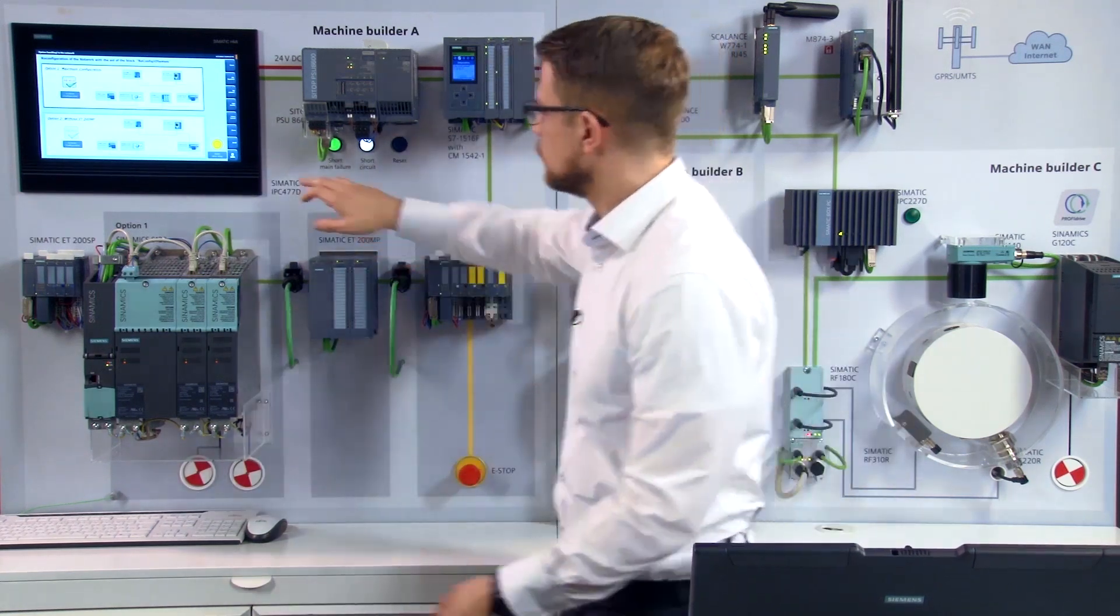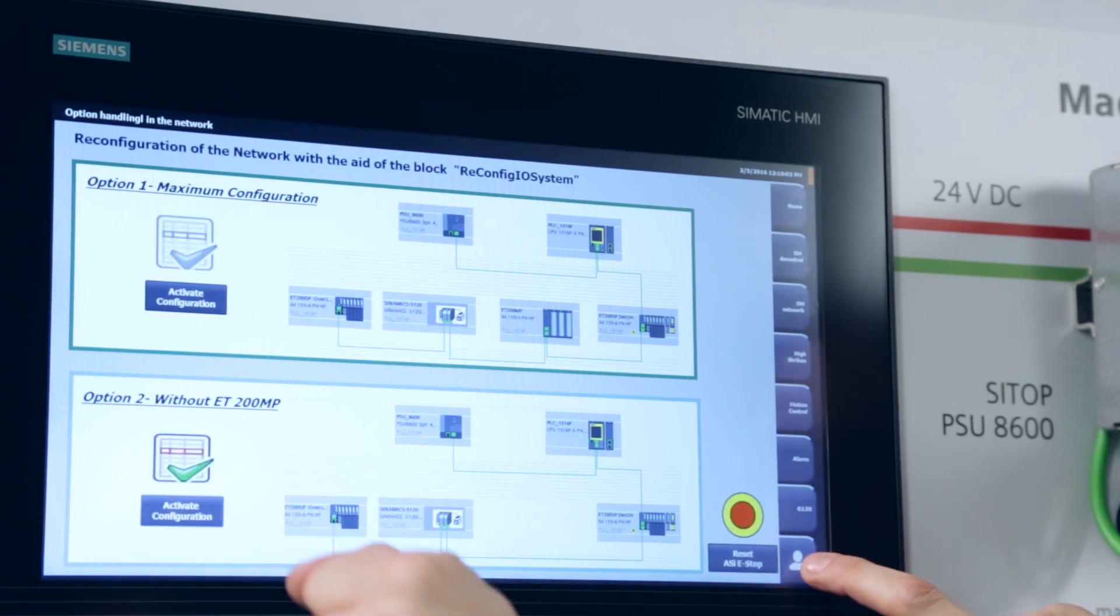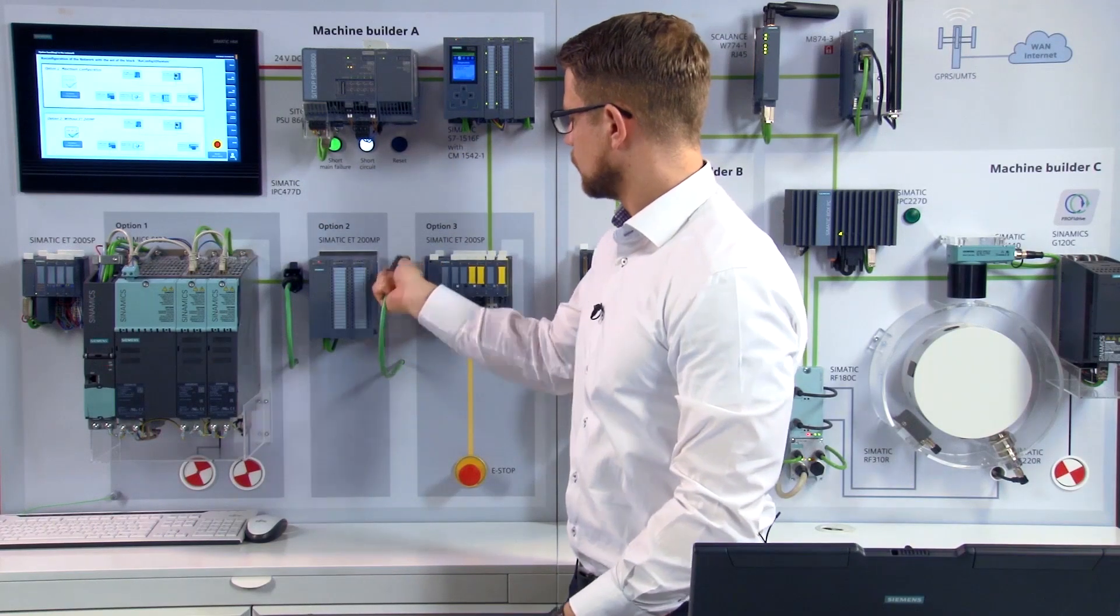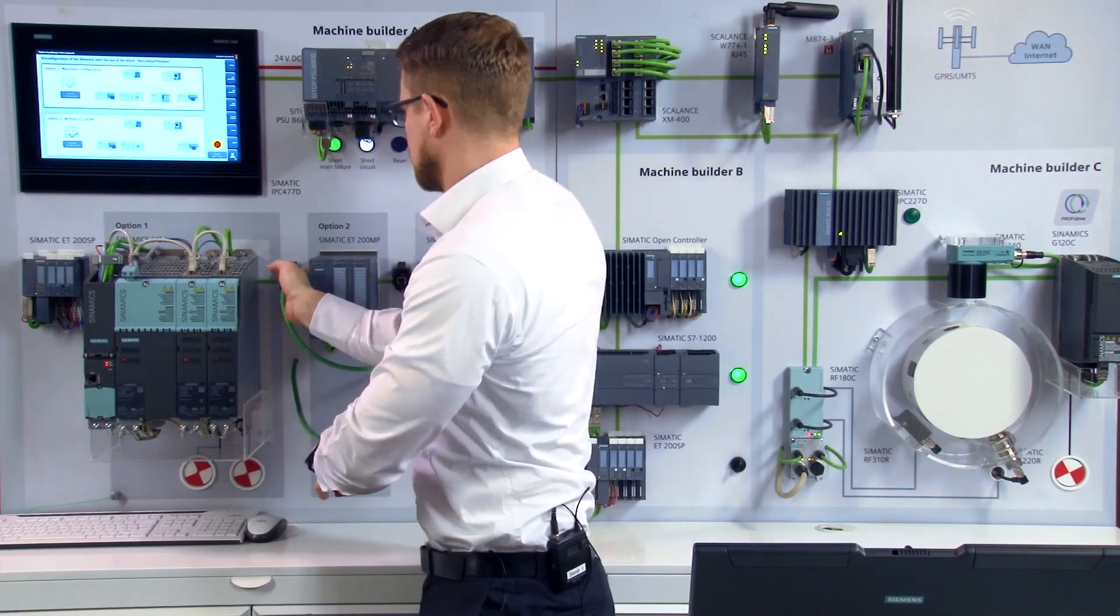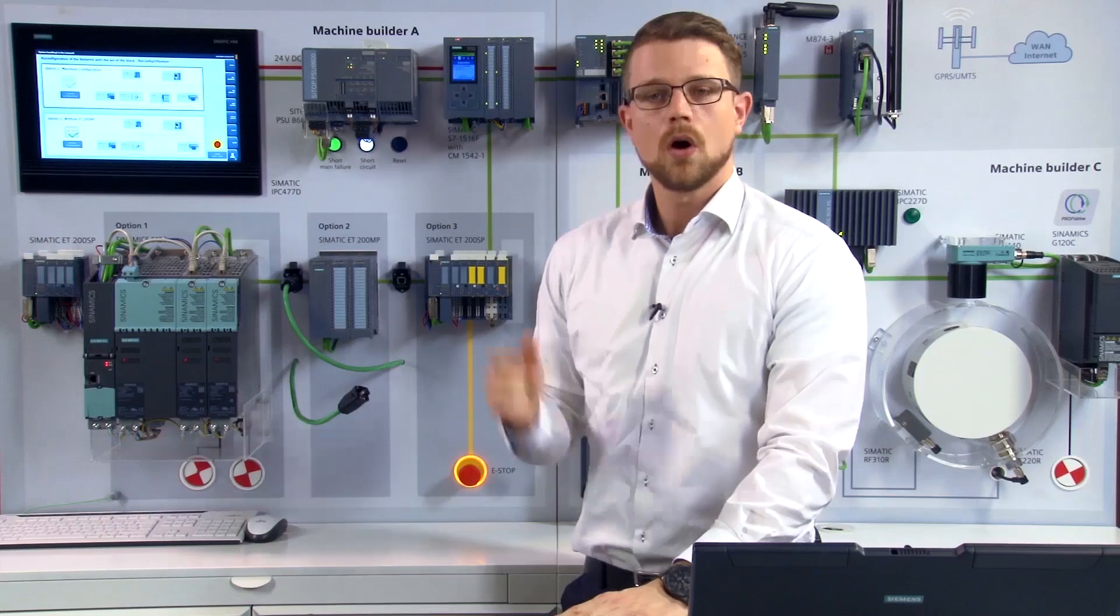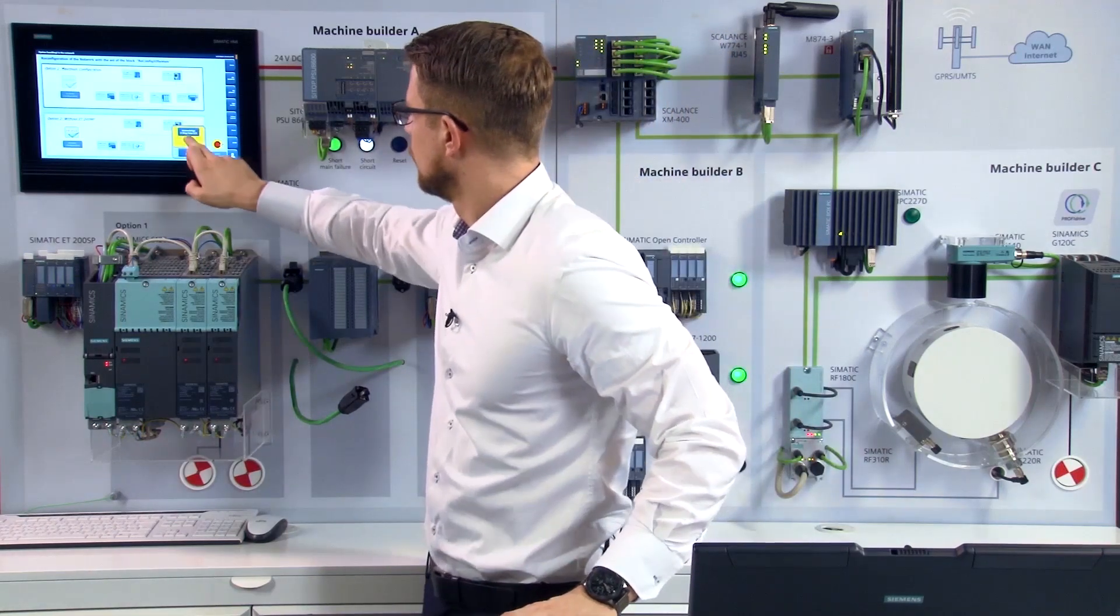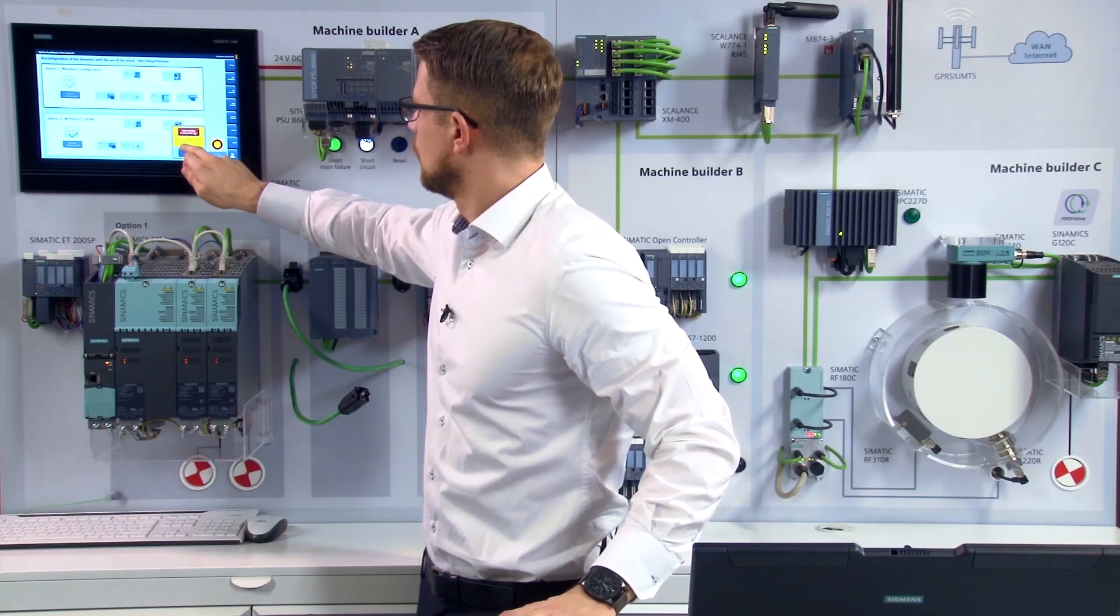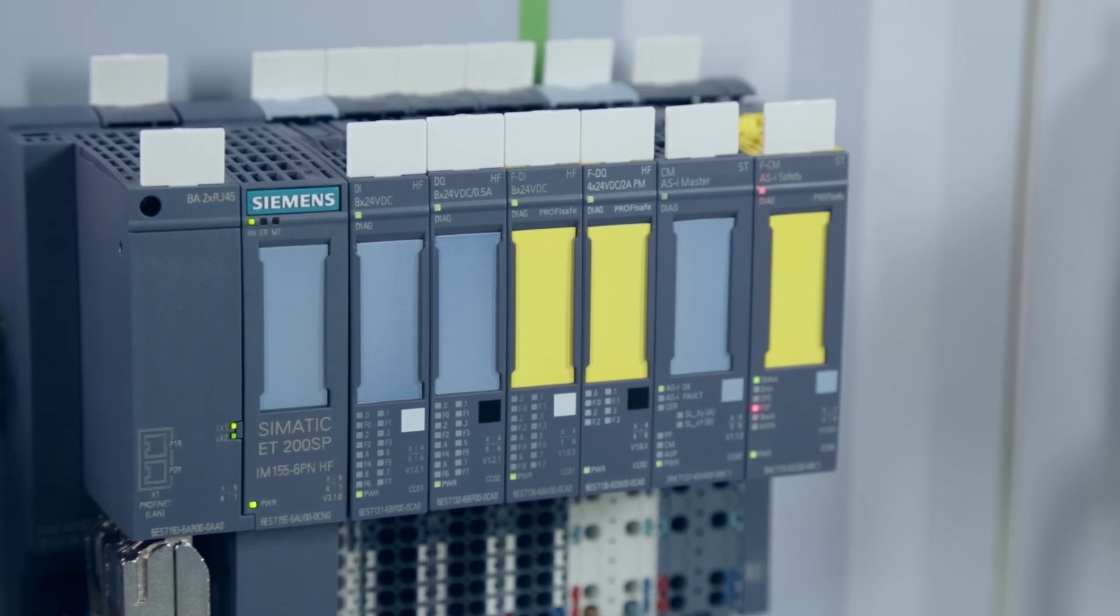During commissioning, it's important to remove the material infeed, in this case the ET 200 MP, according to customer wishes. To do this, I select the associated option. Do some rewiring to bypass the ET 200 MP and repeat the safety acknowledgement process. As you can see, the machine is ready for use.